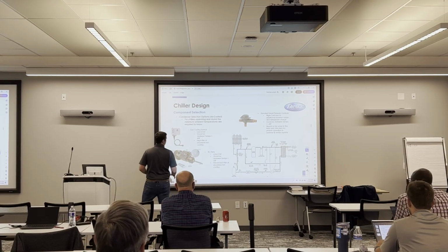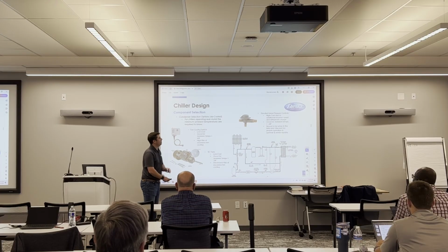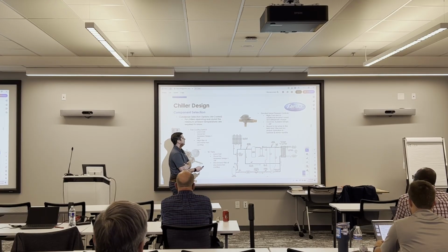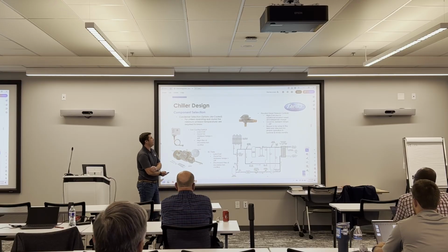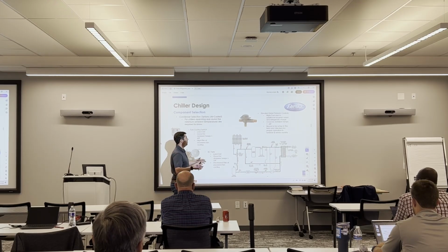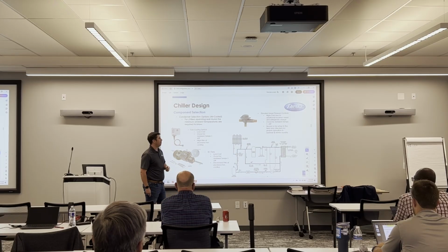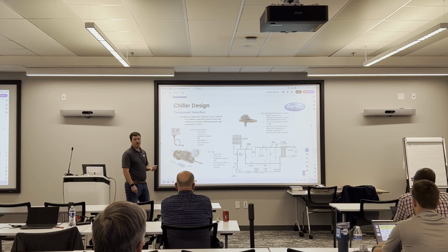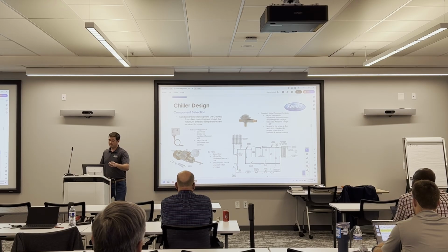So that's fan controls. And if you need to run it in ambient temperatures lower than 10 degrees, we also offer flooded head pressure controls. That's good down to about negative 40 degree ambient. That is going to come with a high cost, just due to the additional components you're going to need. You're going to have to add a big receiver vessel to store this refrigerant. You also have to account for the refrigerant charge you're going to have to add to the system. Generally, when you add a receiver onto a chiller, your charge is going to almost double. And refrigerant these days, as you guys probably know, is very expensive.